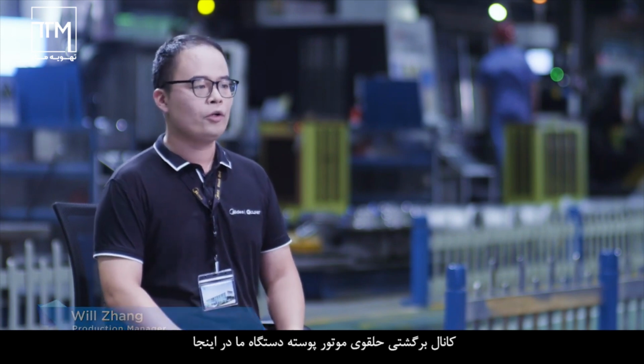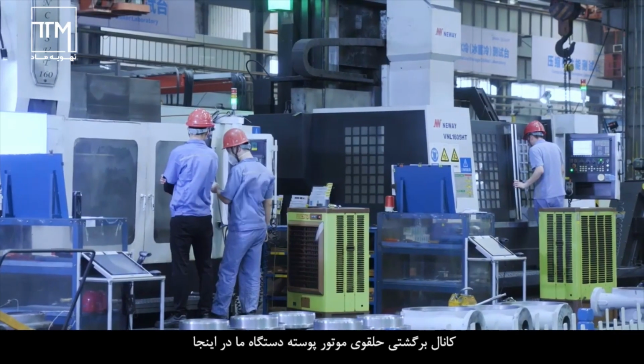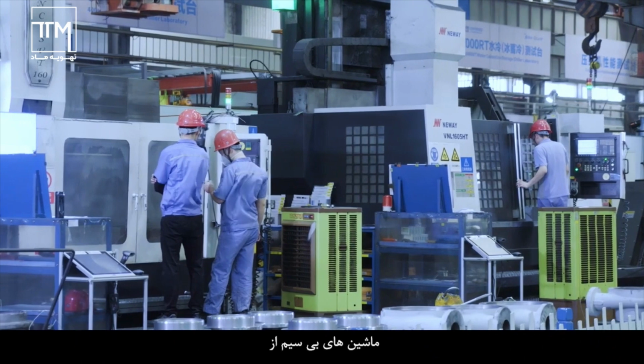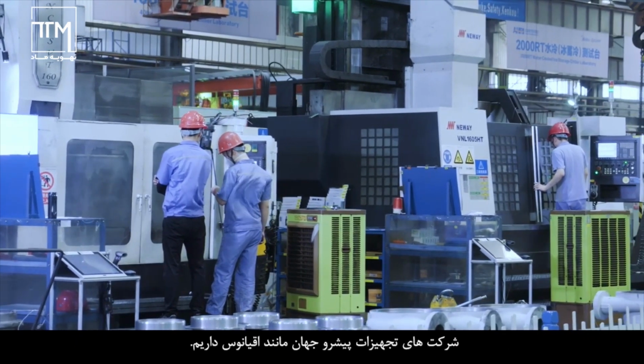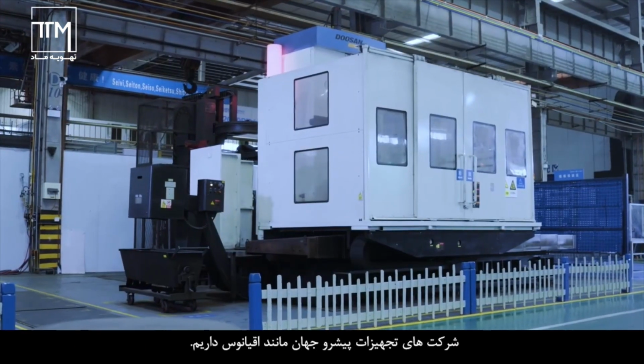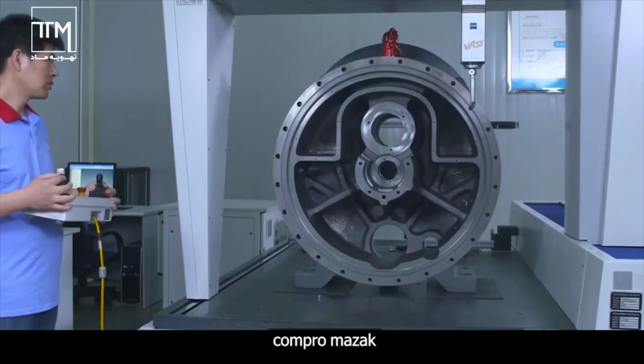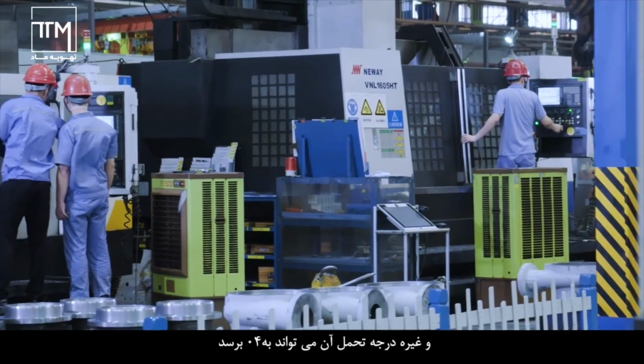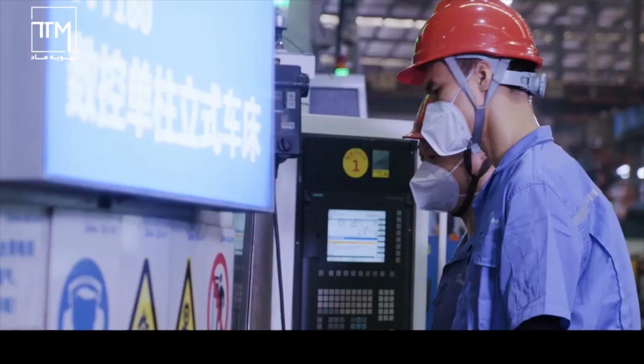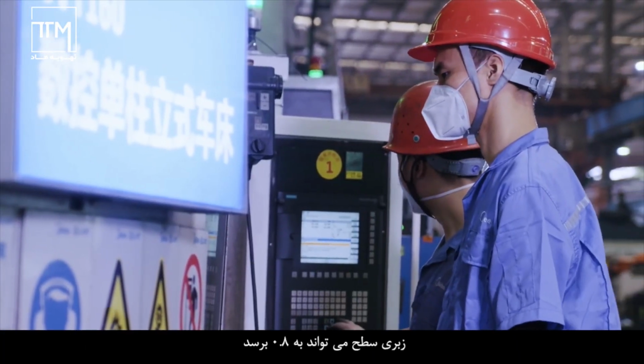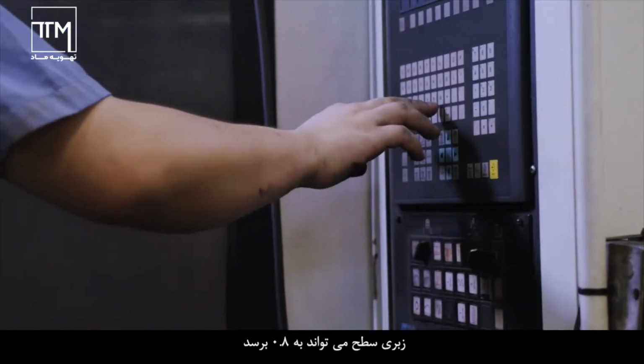Now we are in the compressor manufacturing center. All the key parts, like the volute, return channel, and motor shell, are machined here. We have various machines from world-leading equipment companies like Doosan, Compro, Mazak, etc. The grade of tolerance can reach IT04. The surface roughness can reach 0.8 in order to guarantee the assembly accuracy.